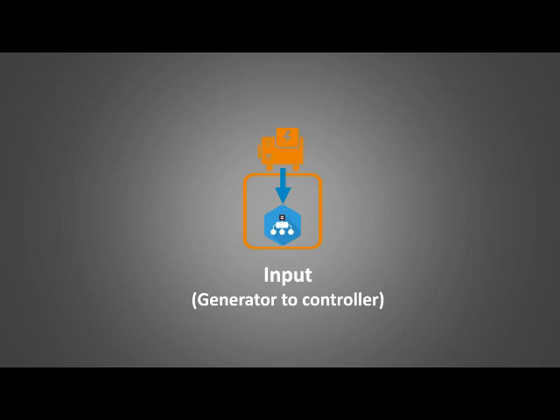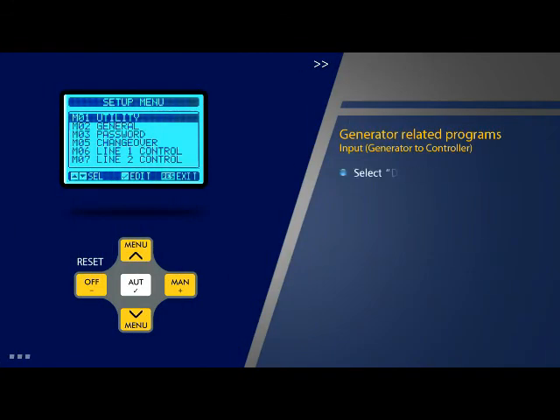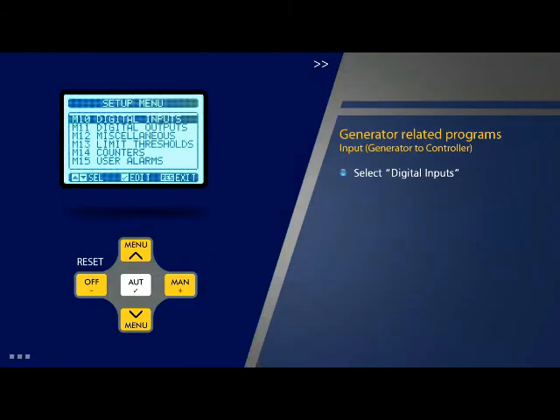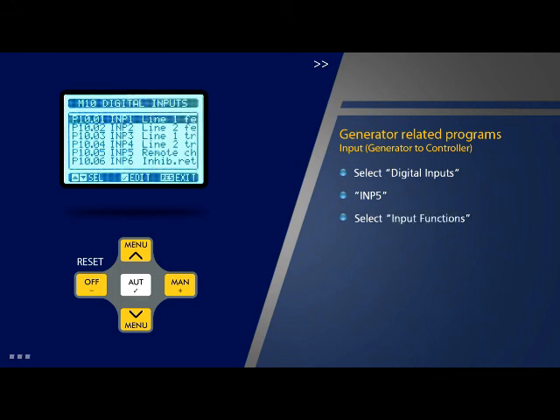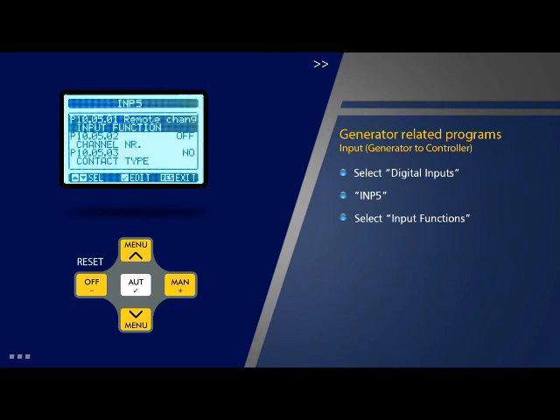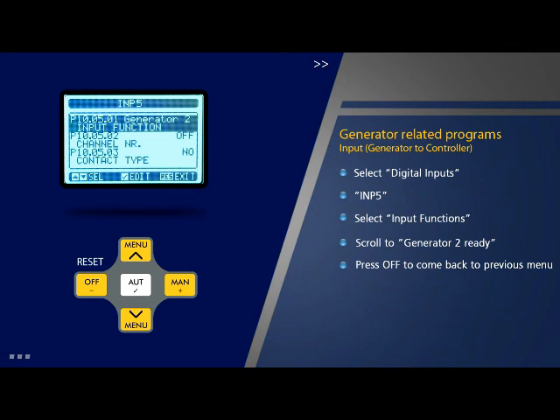Input generator to controller: Feedback from the generator is to be connected to terminal 19 of input 5 of the controller, and programmed as follows. Select parameter 10 'Digital Inputs' on the setup menu page and press OK. Scroll to option 5 which is INP 5 on this page and press OK. Select the first option 'Input Functions' on this page and press OK. Scroll to select the option 'Generator 2 Ready' on this page and press OK. Press off to come back to the previous menu. The option 'Generator 2 Ready' is now selected.